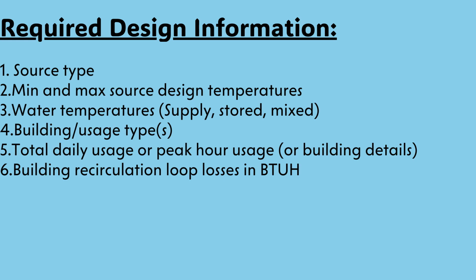Basic information on the system parameters is required for sizing a system. Source type, air or water. Water temperatures: cold water supply temp, stored hot water temp, mixed water temp. Building type: office building, multi-use, multifamily, hospital, school, etc. Total daily use. If you don't know, we have tools to help you determine the loads. Ultimately, this is the responsibility of the specifying engineer. Building loop losses, min flow of mixing valve, including GPM and delta T, BTU/HR = GPM x 500 x delta T. It's a constant drain on the system and must be made up or absorbed during non-use periods.